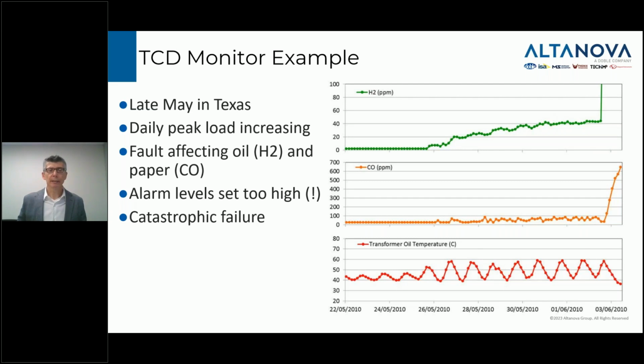And around the second day, around the 26th of May, we started seeing hydrogen and to some extent carbon monoxide being generated. So a fault had emerged. It was being detected by this TCD fault detection monitor. And it progressed over the course of a week or two. And tragically, what happened is the transformer failed. The first time we saw this data was after we were cleaning up after the transformer failure. So the main lesson I want to share with you from this example is maybe two things. First of all, a very sensitive hydrogen detector. We could have detected, when the concentration reached 5 ppm, maybe 10 ppm above a historical baseline of 0.